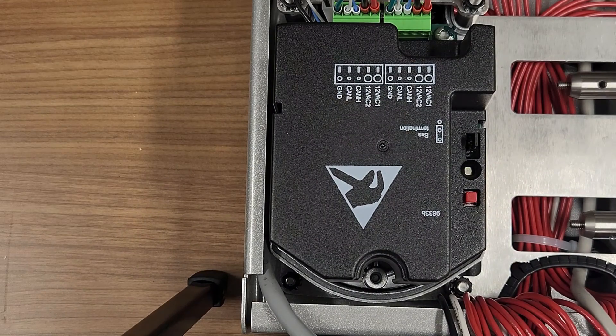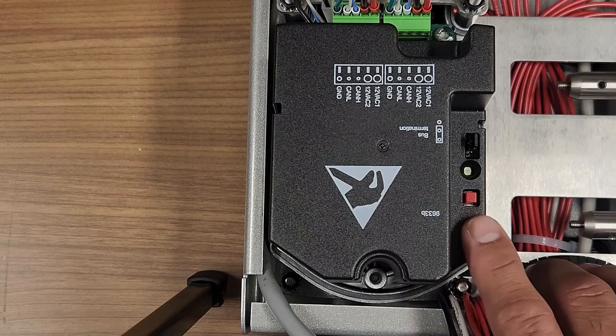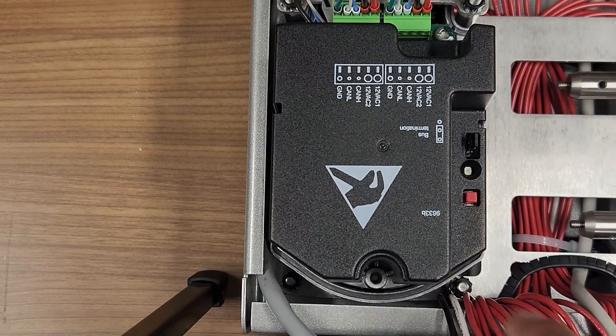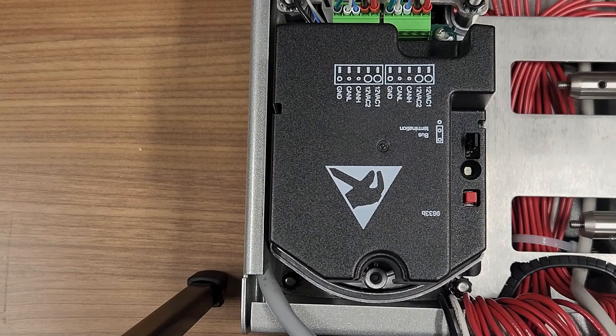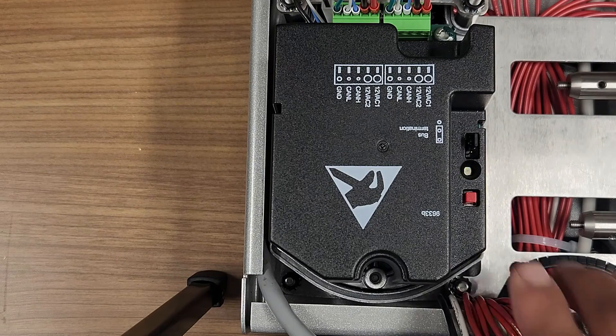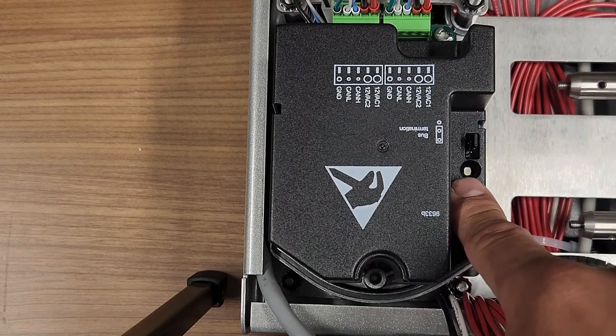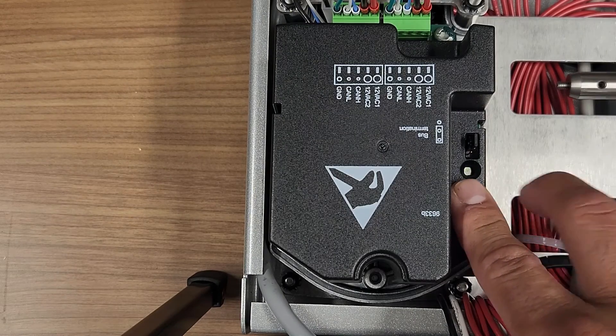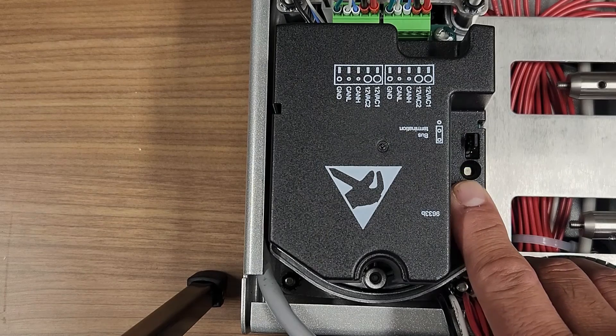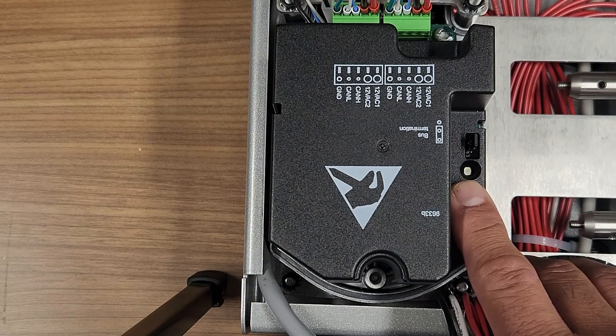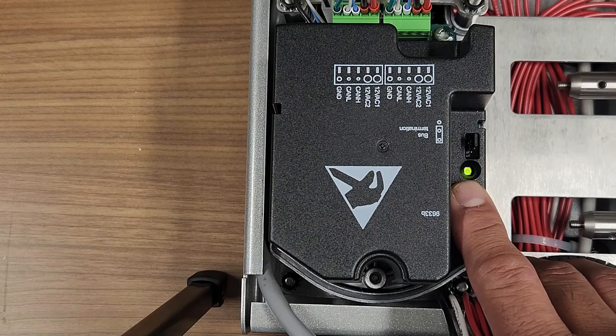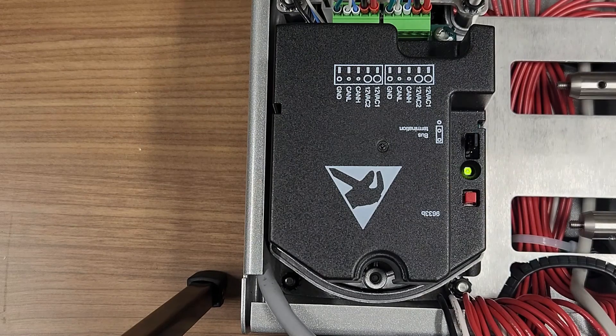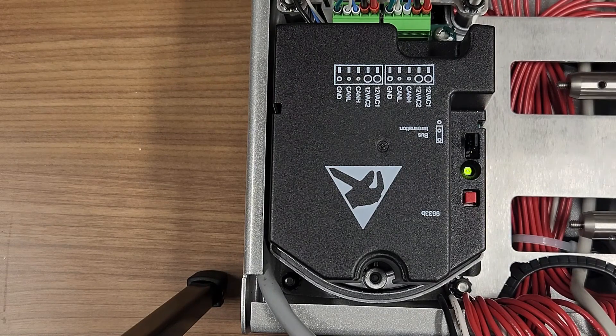If for some reason you held that red button too long or addressed the wrong actuator, you can actually reset it by holding down the red button for approximately 10 seconds, which will then clear the actuator. We're going to press and hold down the red button for approximately 10 seconds. Once we see that green LED turns solid, we will then release. Release and a solid green LED will confirm this request.